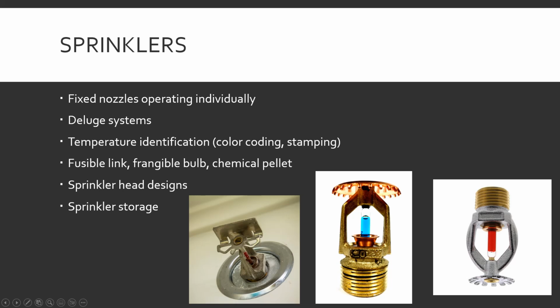Sprinkler storage. If you remember at the beginning when we talked about the fire command post, that's that little red box that has a wrench and spare sprinkler heads. Now, according to the rules, I believe a place is supposed to have like 3 of each kind in the building. So if they have all of these, they'd have 6 or 9 in the box. 3 of these, 3 of these, and 3 of these. And the wrench and anything else that's important to changing these. Now, it depends on policies. The department may change these. They may shut off the water and kind of help clean up the mess, but it's building maintenance that has to change them, or the building has to contact whoever installed or services the system, and they have to come out and do it. It's all kind of preferences kind of thing.